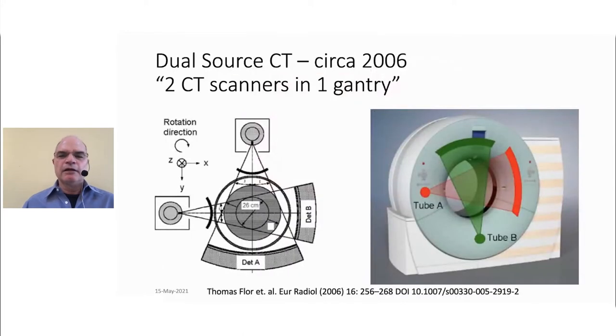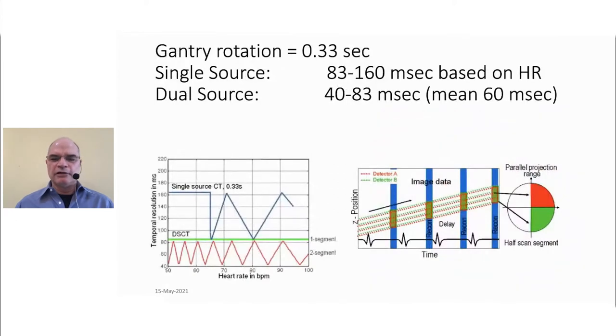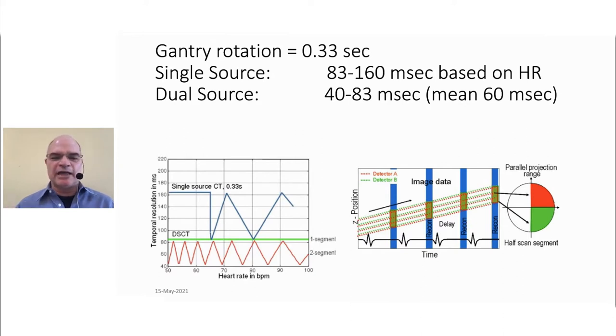In 2006 came the advent of the dual-source CT, which is effectively two CT scanners within one gantry — an A tube and A detector, and a B tube and B detector. This two-CT-in-one allows us to gain dramatically in temporal resolution compared to a single tube-detector combination. With a single-source CT scanner rotating very quickly at 0.33 seconds per rotation, the max temporal resolution is between 83 and 160 milliseconds. Today, with even faster gantry speeds, we routinely image the heart at 66 milliseconds per image.